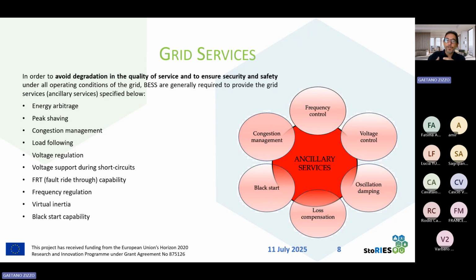So the services in which battery storage systems are usually adopted are energy arbitrage, peak shaving, congestion management, load following, voltage regulation, voltage support during short circuits, fault ride-through capability, frequency regulation, virtual or synthetic inertia, and black start capability. Now, we will introduce one by one these services for making more clear how for each service a storage system can be used, what it can provide to the grid, and so on.